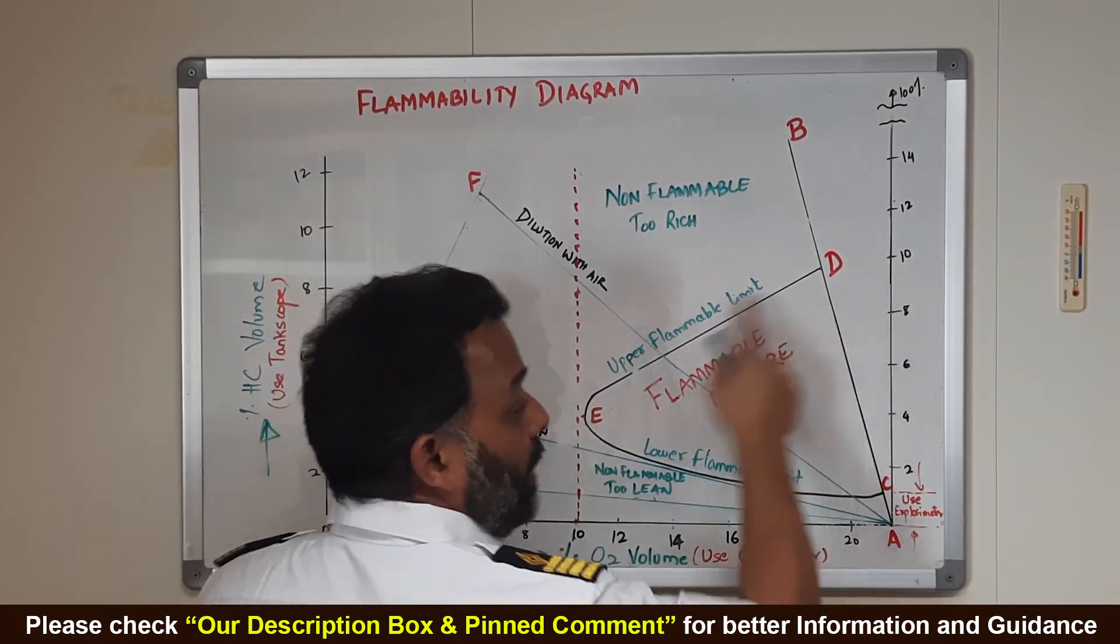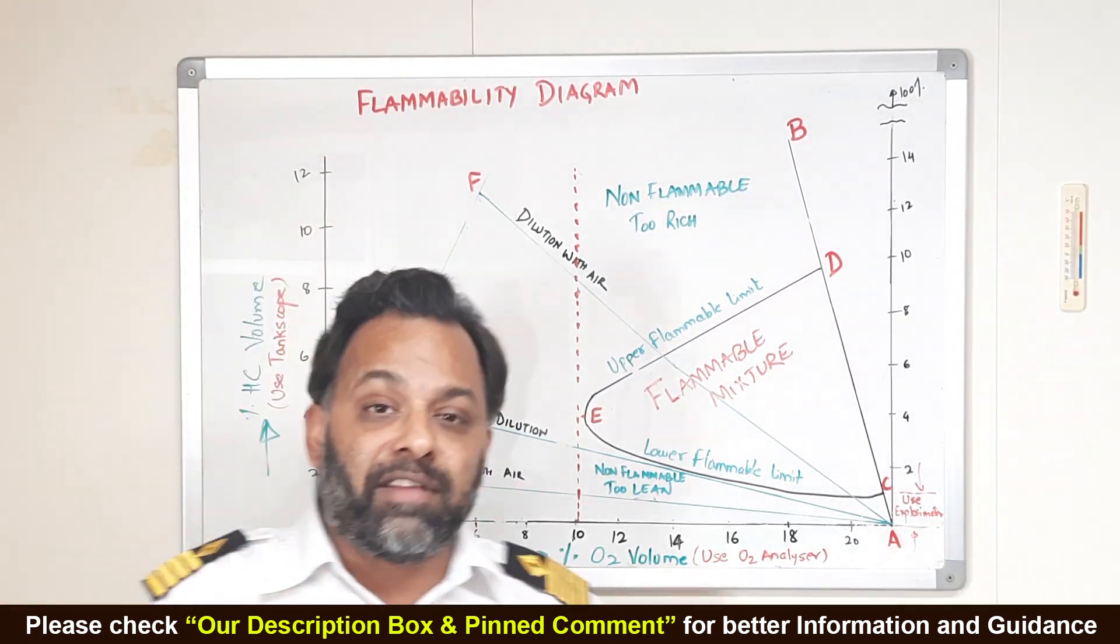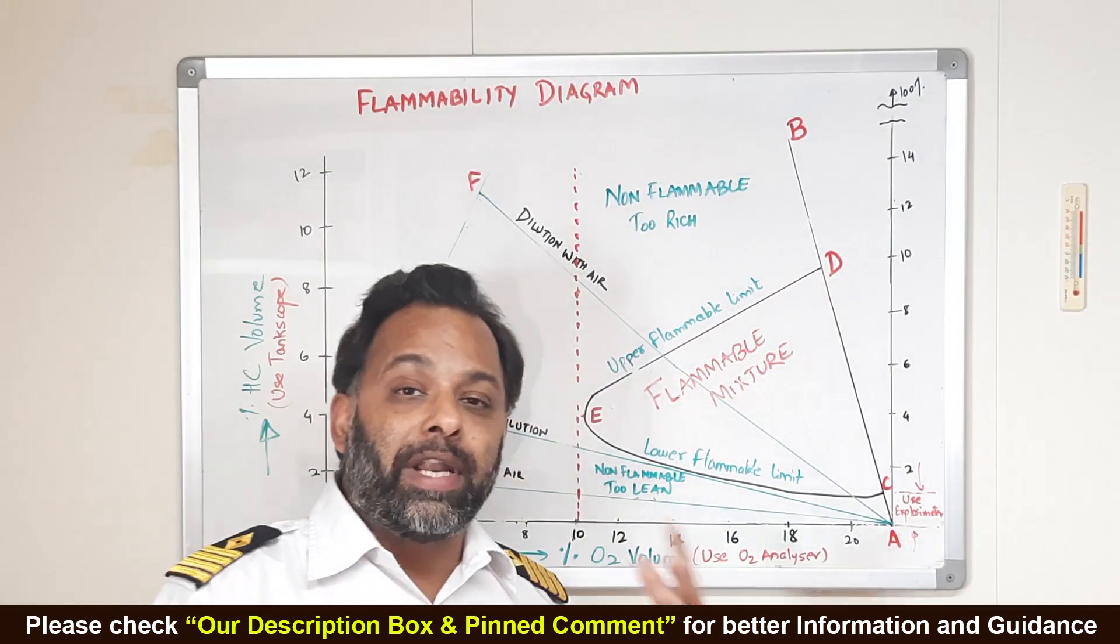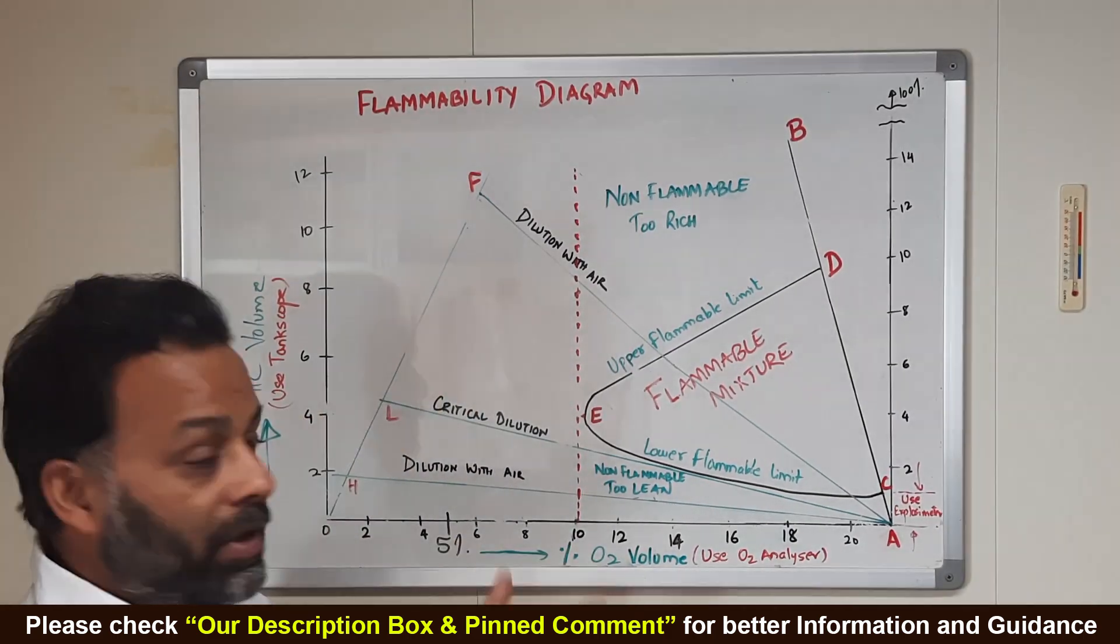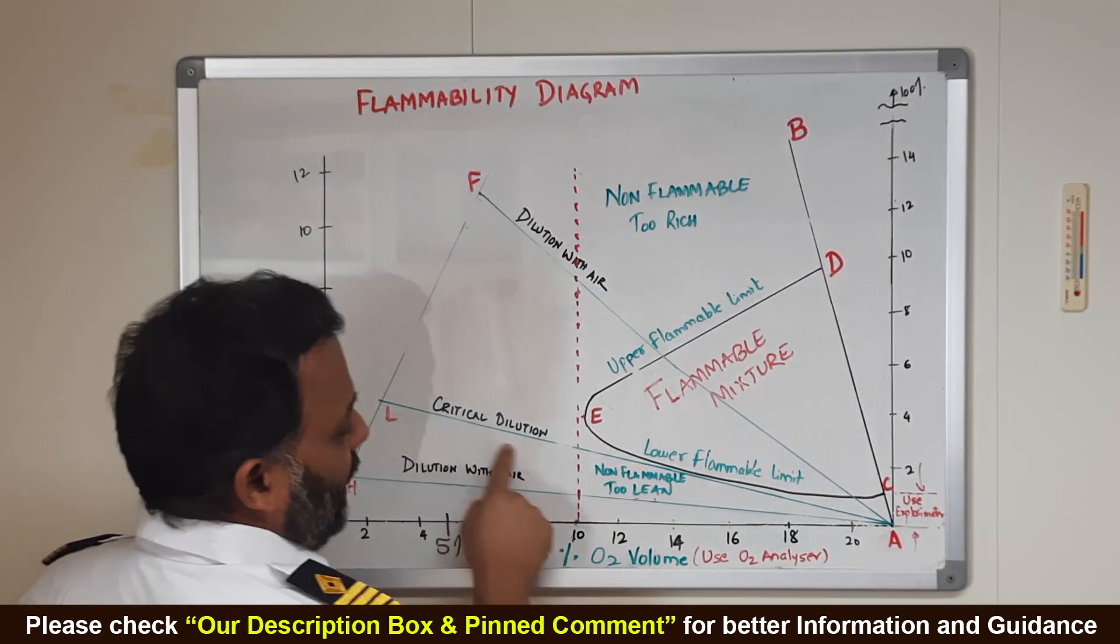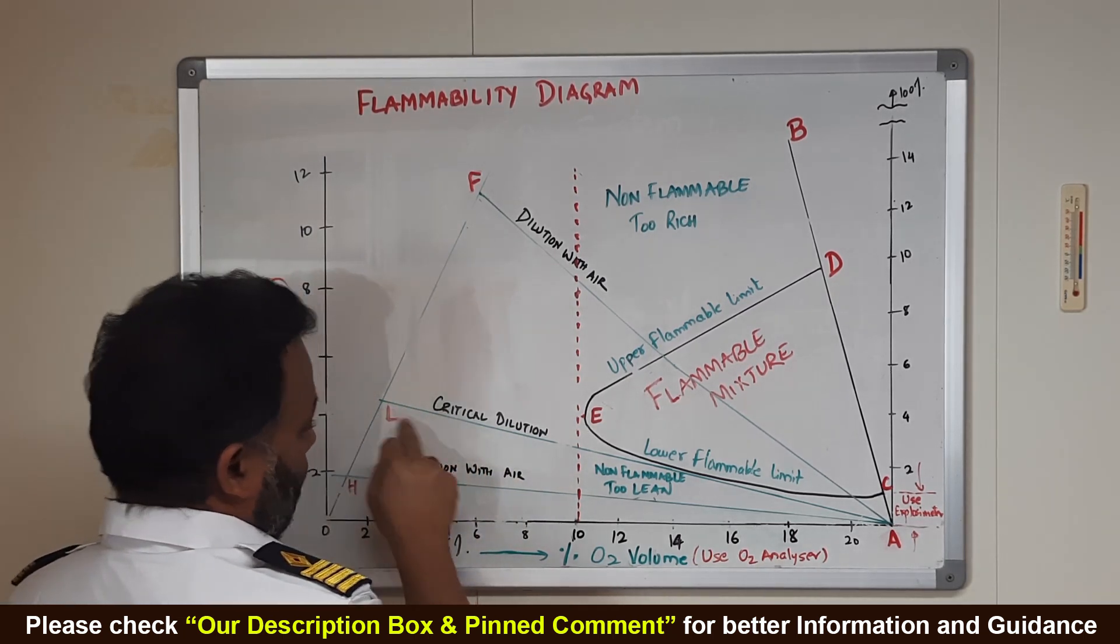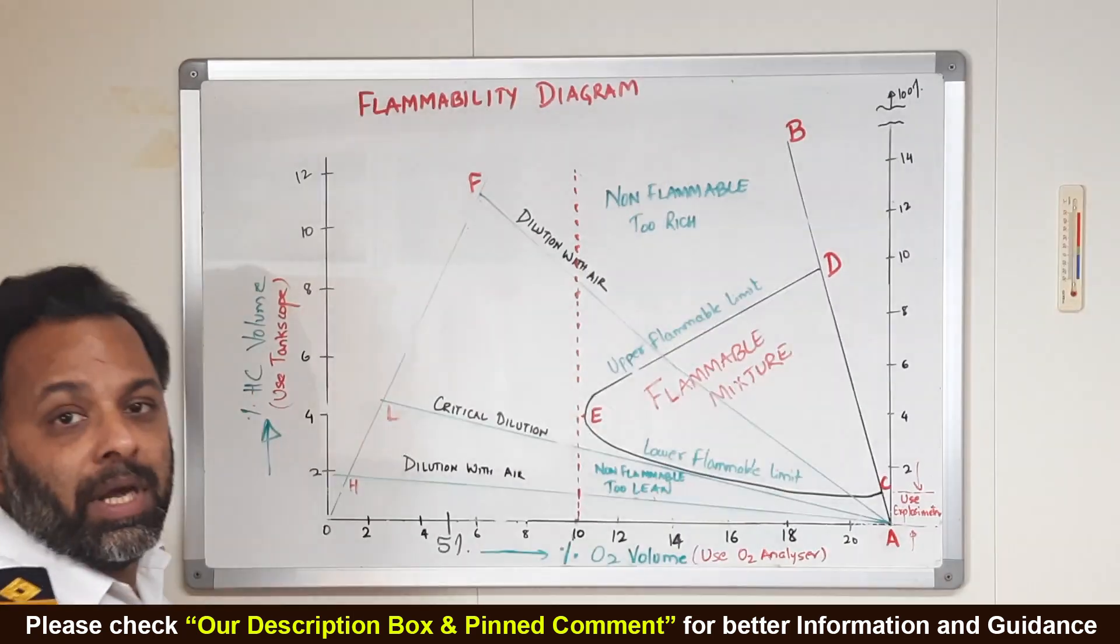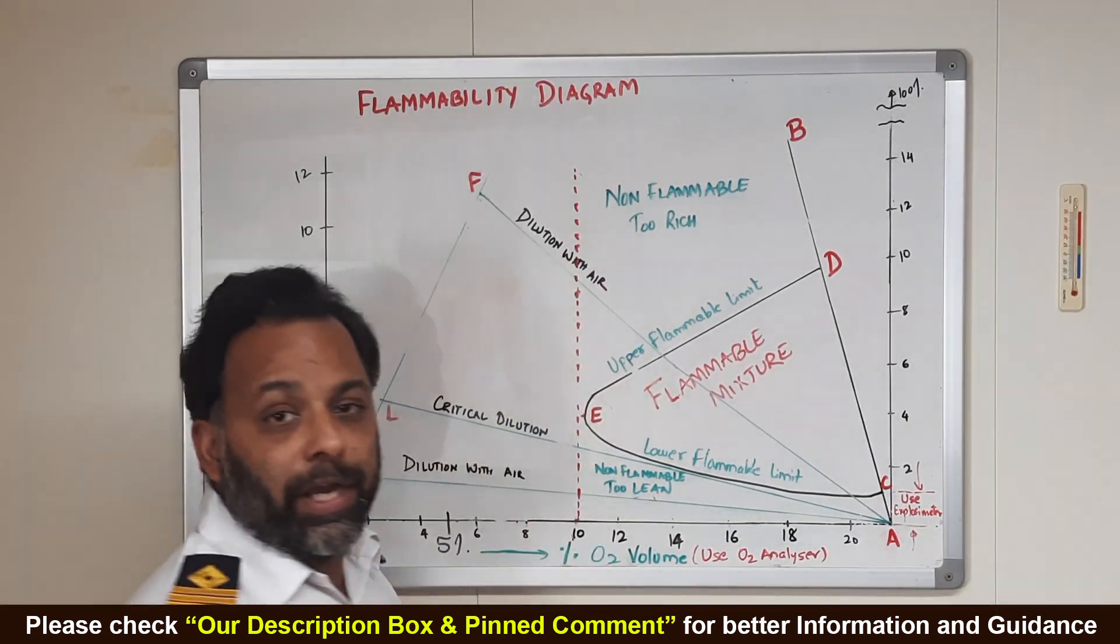So, flammability diagram tells us how to avoid this flammable mixture region so that we do not have any time where we go through this flammable mixture region. This is the critical dilution line, this is the maximum dilution of air which is just clear of this flammable region. But it is better to go further down as much as you can and then introduce air into the system.